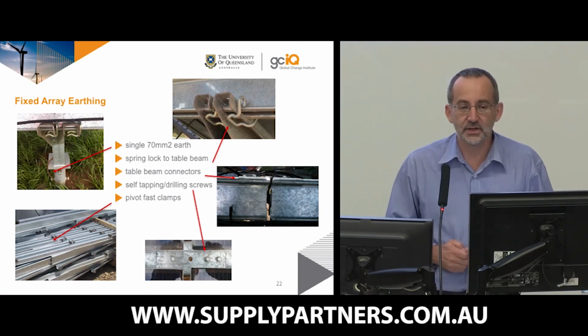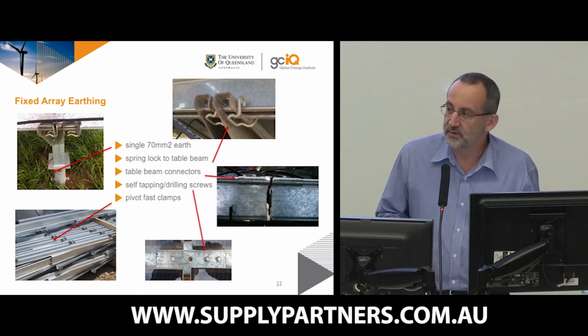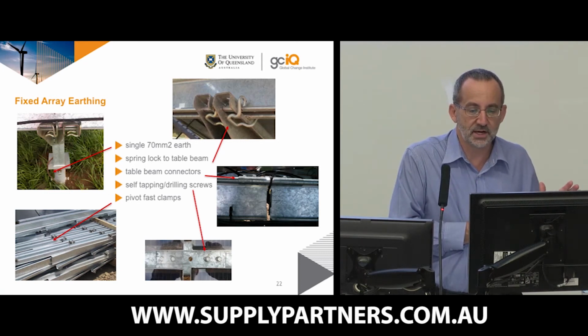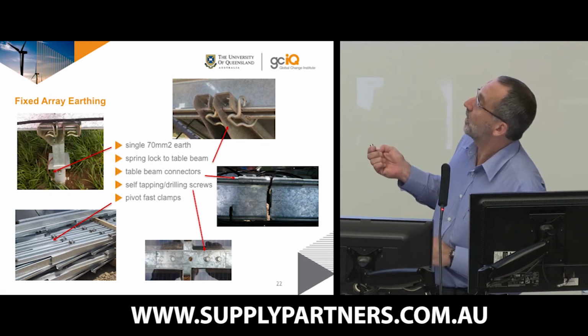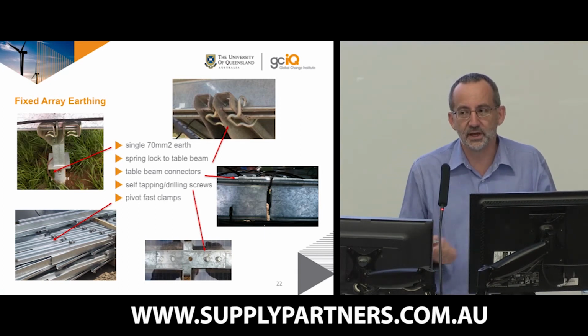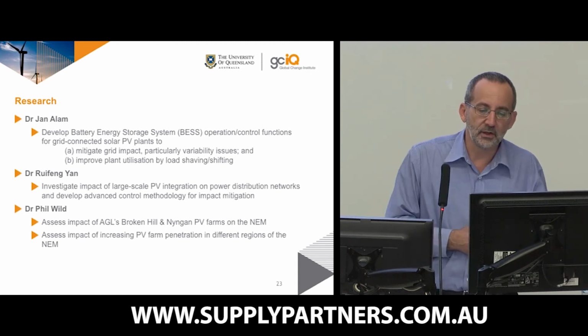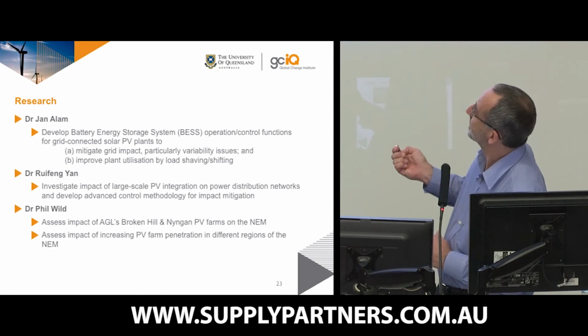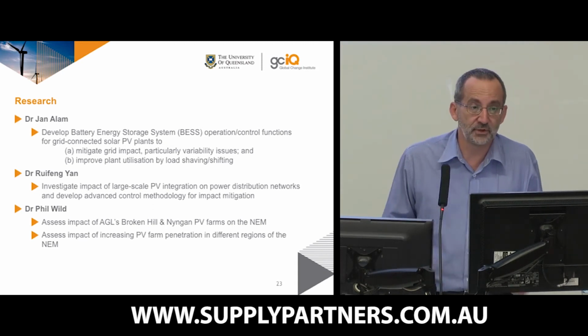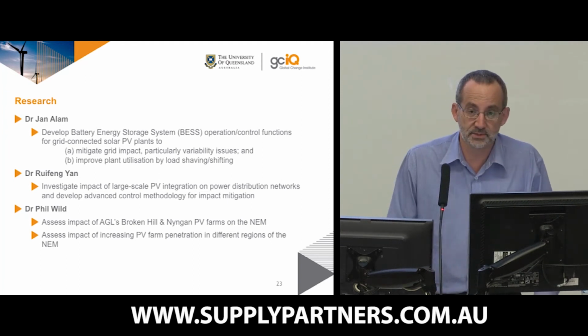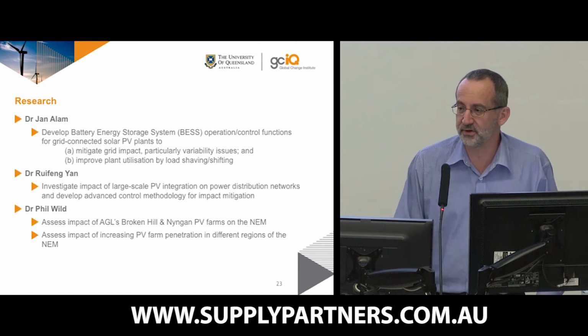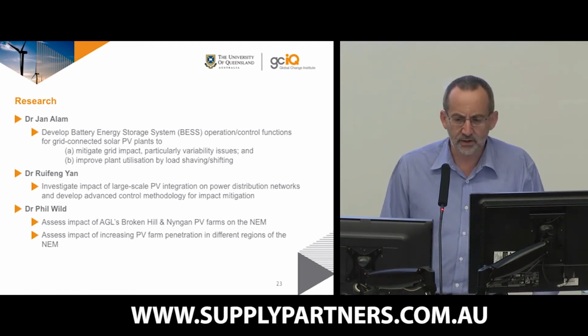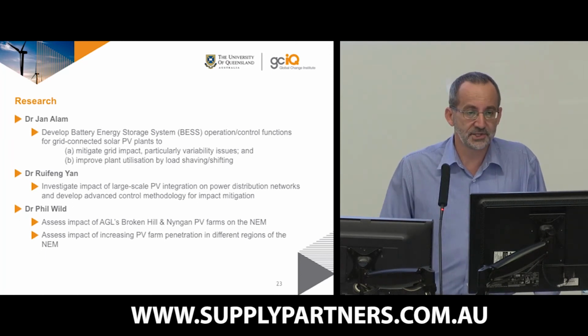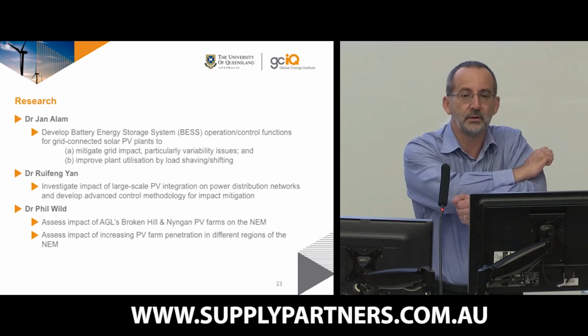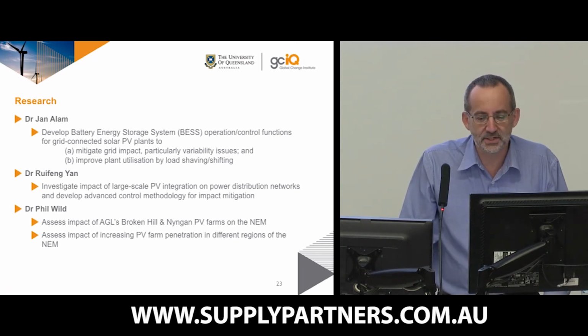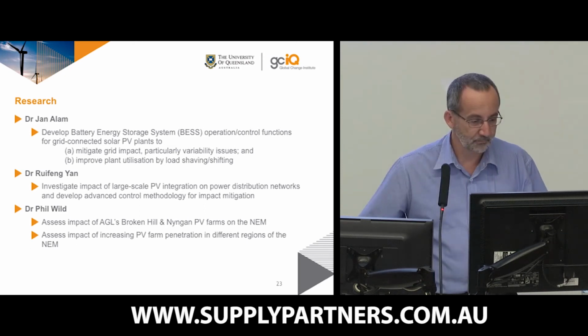So we've also got some interesting earthing arrangements. You'll see, going clockwise, we have a single earth on the fixed axis arrays. It's coupled to the horizontal beam by some spring locks, which allow for some lateral movement. That is then coupled along the whole array by some beam connectors, which are held in place by self-tapping or self-drilling screws, which is something that in the smaller systems we're certainly discouraged from doing. 5033, in fact, says that that's not to be done. And finally, the tables themselves arrive in a folded fashion, which means that the cross rails are actually pivoting on a bolt, which is another unusual method of earthing. So it remains to be seen how they handle long term.